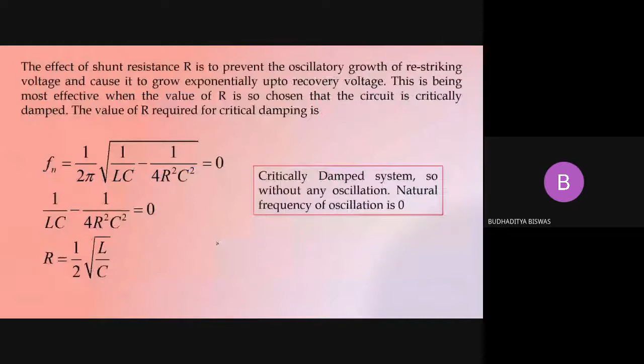And from here we can get an idea about the resistance. If the resistance across the circuit breaker contacts becomes half root under L by C, then the system becomes critically damped. And as the system becomes critically damped, there is no unwanted oscillation across the circuit breaker contacts. So this is called the resistance switching, and this resistance switching is there to prevent the current chopping.